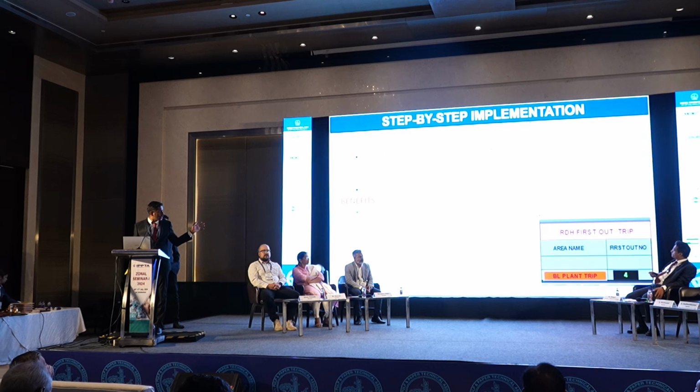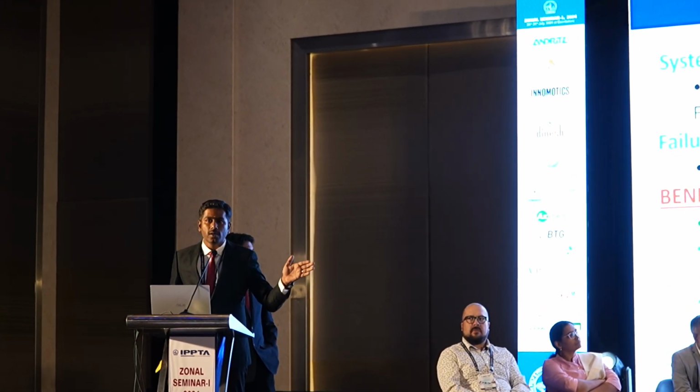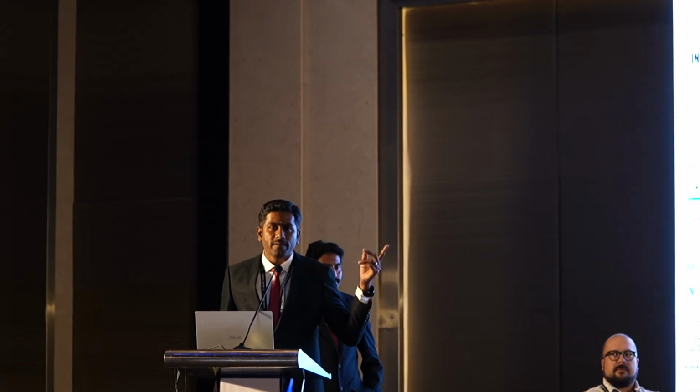This feature connects all the interlocks to the FIFO block. So the FIFO block reflects which cause, with the particular pin number, on the next page. So we can easily identify which cause led to the failure. So this is the use of the FIFO block in DCS. It's one of the troubleshooting measures for us.